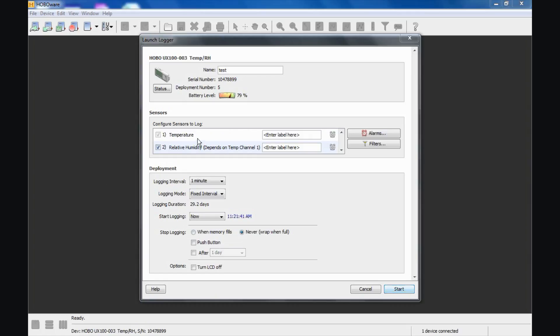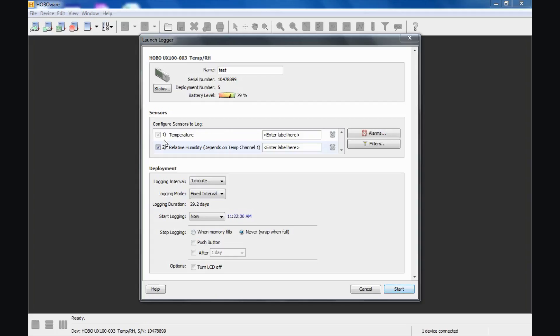Notice here we have two sensors available. This has two sensors inside: temperature and relative humidity. When relative humidity is enabled, you cannot disable temperature. That's why that checkbox is grayed out. That's because temperature is required for determining relative humidity.